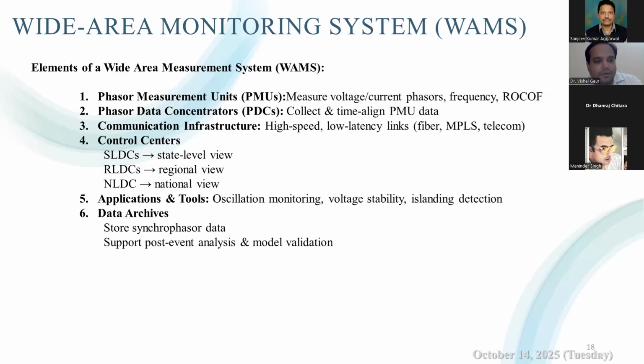I already said that the wide area measurement system is an integrated system having PMU, PDC and everything. I have discussed briefly the PMU, PDC, and the function of PDC. Here we also require communication infrastructure that should be capable of exchanging information with high speed and low latency. For that purpose, we utilize the optical ground wires in our power system, OPGW. Similarly, once data reaches the PDC, it is forwarded to the control centers which operate at different levels, meaning state level, regional level, and national level.